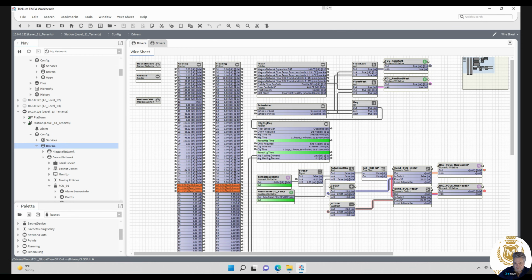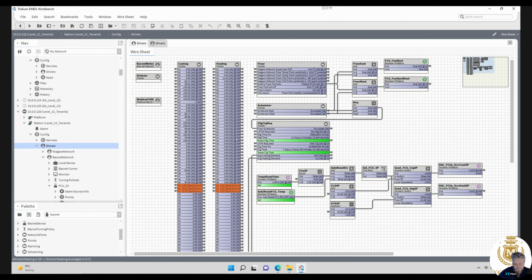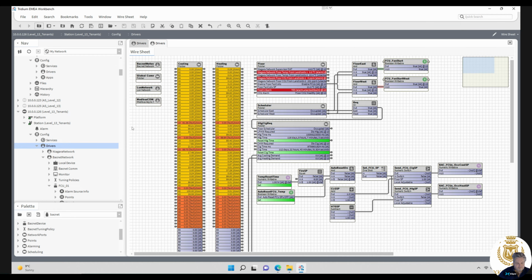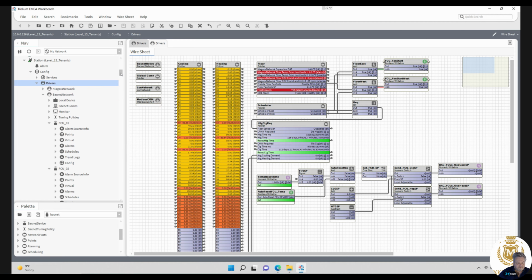Where's that coming from? I actually wrote the logic, but it's been a while since I've written this. So, fan coil global set point from driver's floor. So I have forgot, and I only looked at this last week as well. But other sites and other works, you just forget. So we're on level 13. We can't get mixed up now between a level 11 and 13, so let's just close that down, and I'm just going to minimize the BACnet.